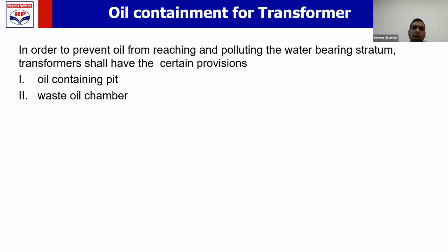चलो आग लगी तो क्या करेंगे, पर क्या हुआ, ट्रांसफॉर्मर में आग नहीं लगी है पर उसका ऑयल लीक हो गया. ऑयल लीक हो के जा रहा है. Then what needs to be done? To prevent the oil from reaching and polluting the water bearing stratum, the transformer shall be provided with certain provisions. Certain provision क्या है? Oil containing pit and waste oil chamber. दो चीज लगानी पड़ेंगी, oil containing pit and waste oil chamber. Where the oil containing pit will be provided and where the waste oil chamber will be provided, and how the waste oil pit, oil containing pit and waste oil chamber will be connected and designed, let us see in detail.